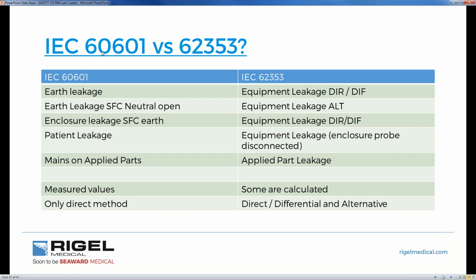Where is the comparison? In 60601, we have earth leakage. Earth leakage is either differential or direct. That's like for like. Earth leakage, single fault condition open neutral in 60601 is our equipment leakage alternative. Enclosure leakage, single fault condition earth, is our equipment leakage, both the same there, you'll notice. Patient leakage is equipment leakage in that the enclosure probe is disconnected, and the return path is via some of our applied parts. Then we put mains on the applied parts as far as 60601 is concerned. The direct comparison is applied part leakage as far as 62353 is concerned.